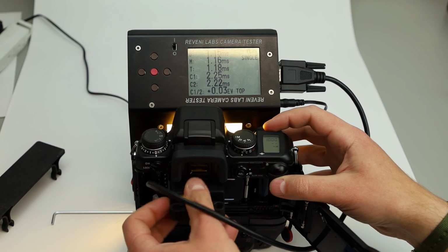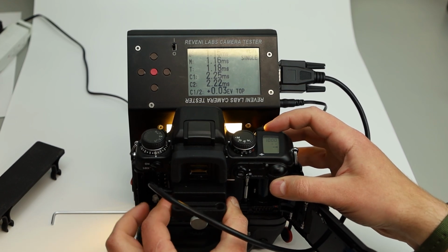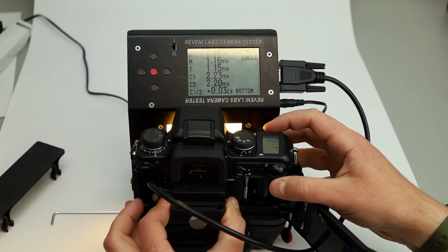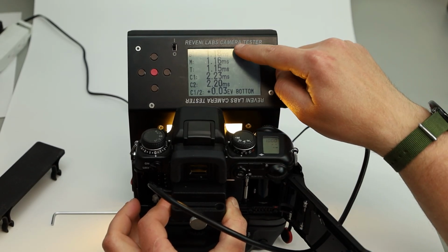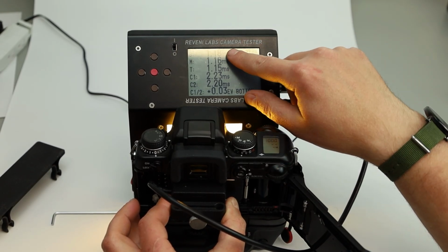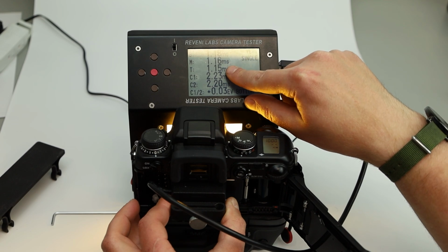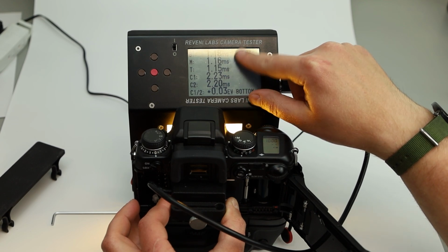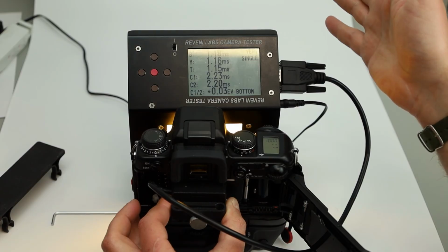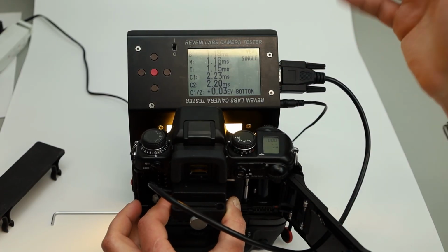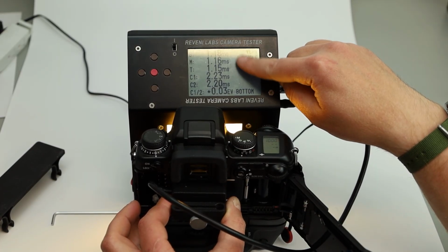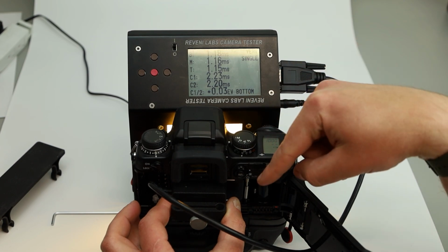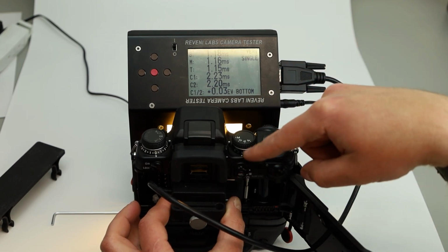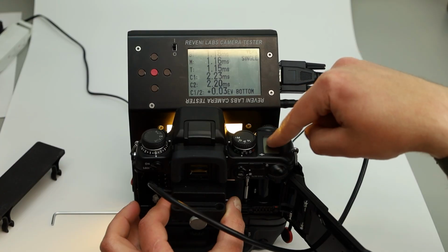Then flip the sensor over so the cable is coming out on the left side. Fire the shutter and observe, in this case, the bottom now shows 1.18 and the top now shows 1.15. So the numbers flipped. This actually indicates that this sensor doesn't need any balancing because the error flipped with the sensor head. That means the error is in the camera itself.